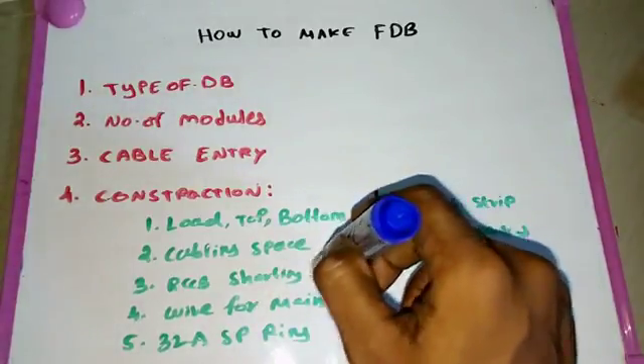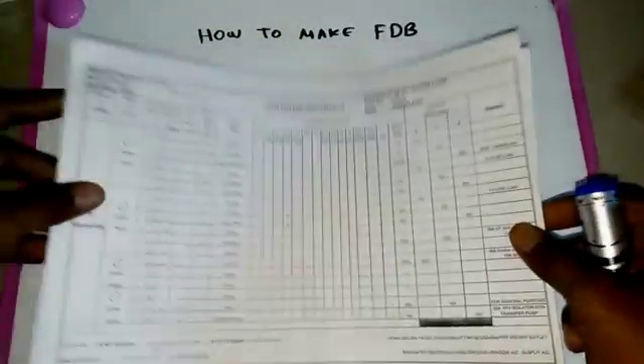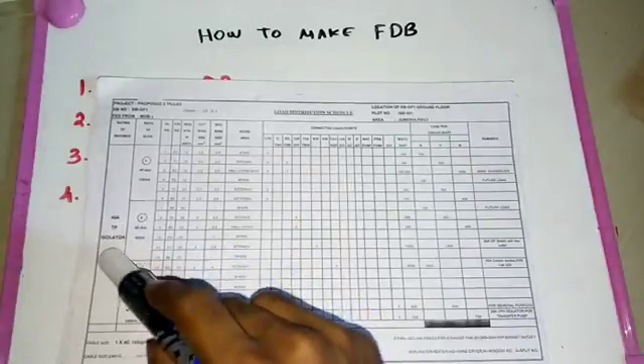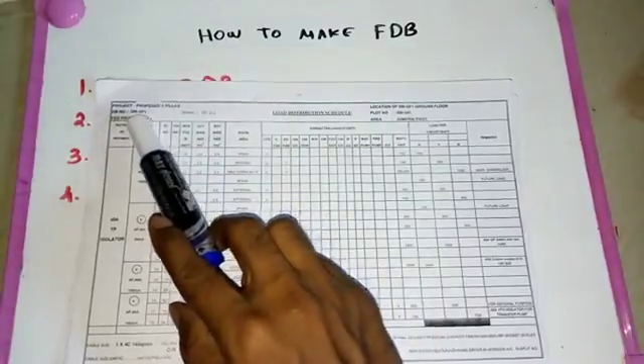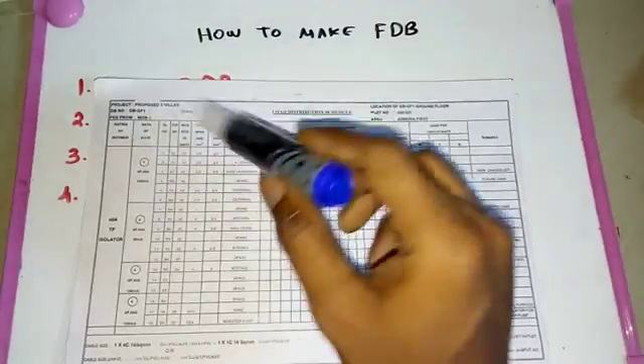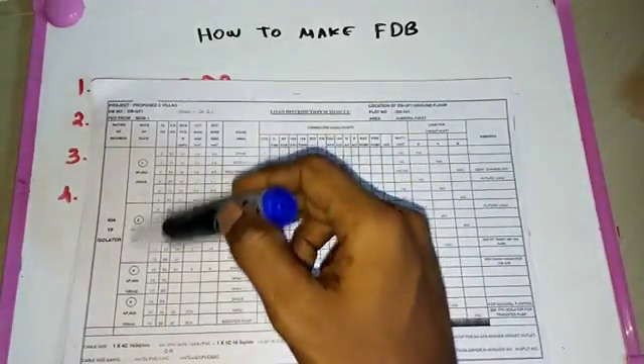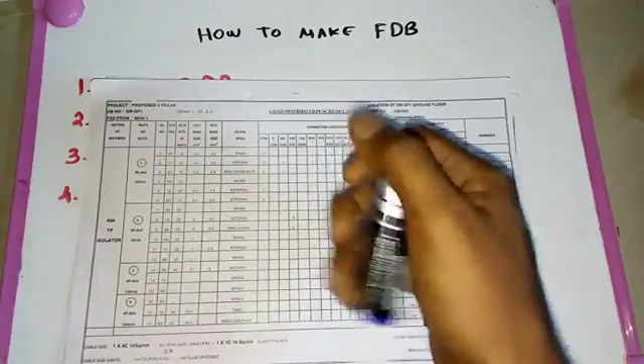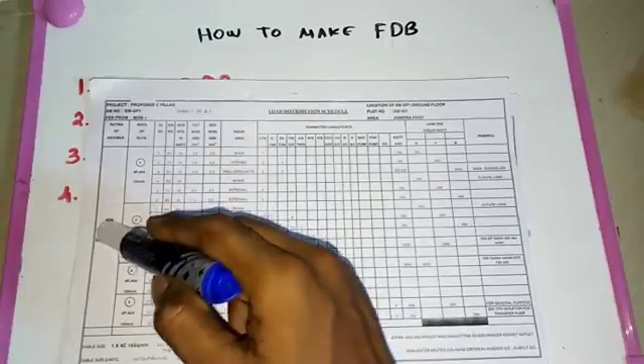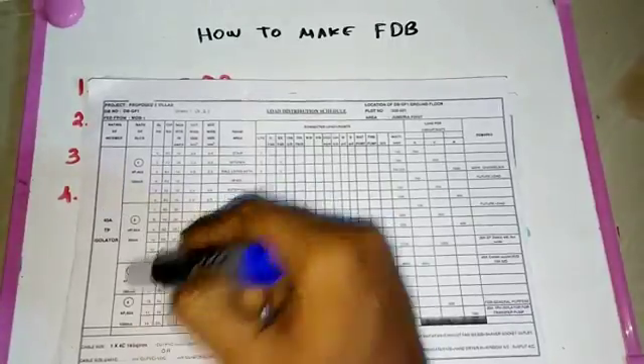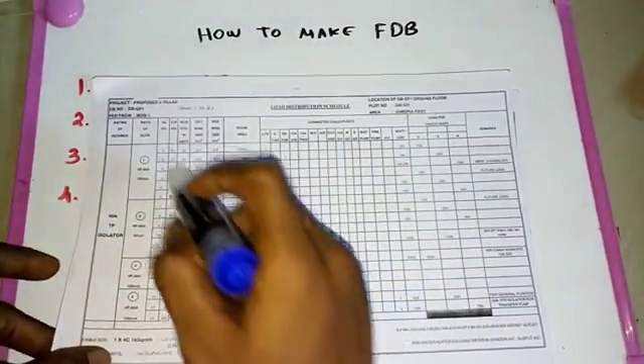RCCB shorting is another important step. In this DB, there are four RCCBs (ELCBs) available. For an ordinary DB, we can short all four ELCBs together using a shorting bus bar — running a wire from the 40-ampere isolator to the shorting bus bar and then to any of the ELCBs.